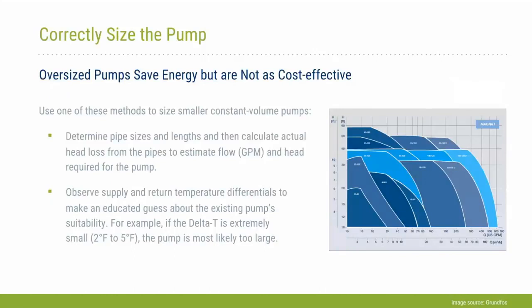Another important point that's challenging for these smaller circulator pumps is they typically don't have differential pressure points or ports. And so you're not able to actually look up on the pump curve exactly where the pump is operating. You're really just looking at what size pump is currently installed. We do have a couple of approaches that could be taken to making sure that you're correctly sizing the pump.